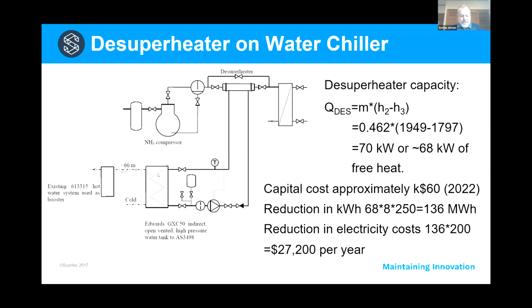That's the one, if you can see my cursor, this rectangle here, because if we were to put domestic hot water or potable water directly through the desuperheater, we get formation of calcium oxide. And this happens very rapidly, within a few months. And if you cannot clean the desuperheater on the water side, you can cut it out and throw it away unless you have an indirect circuit like that.